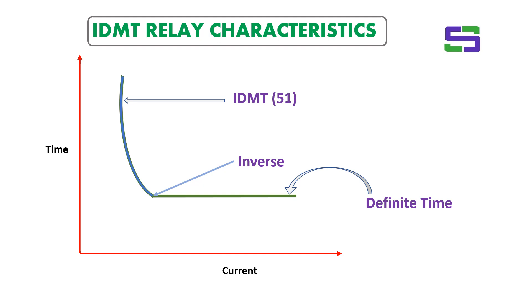After the inverse region, the characteristic becomes just like a straight line parallel to the X axis or current axis. This is the definite time portion. So that completes the explanation of the 51 relay, which has both an inverse characteristic and a definite time characteristic.